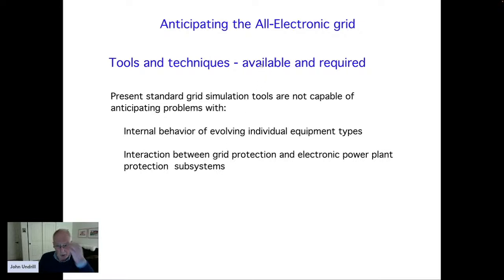The simulations that I showed you were made with the tools available for production use today. They were made with tools that represent the AC electric system by phasor mathematics, where the phasors rotate at either 377 radians a second or 314 radians a second. That's not going to be sufficient to tell us what goes on inside the electronic inverter equipment that's in the loads and the power plants. We need to have an evolution of our simulation technique so that we can see what's going on on the basis of a point-on wave, where the sinusoidal voltages in the system are represented by the differential equations of inductance and capacitance, and the network is going to have to be modeled in an electromagnetic transient level.